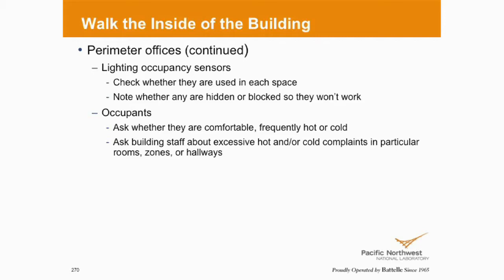Occupancy sensors for lighting. How many of you on your campuses and in your buildings have occupancy sensors, motion-based, infrared? So do we check them? Are they working? Are the lights always on? We may not know because it's probably not on a BAS, but that might be where, when do I do a walk down? We haven't really talked about that. We're going to do a walk down during the day. Is there any value to doing a walk down at night? You bet. Is there any value to doing a walk down on a weekend? You bet. Well, are you going to pay me overtime to do that? No way. So, well, I guess it's not going to happen.